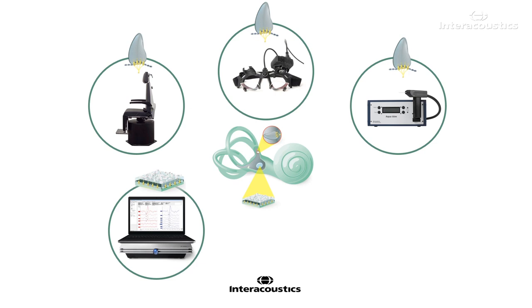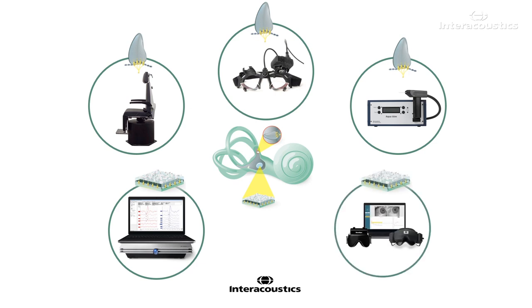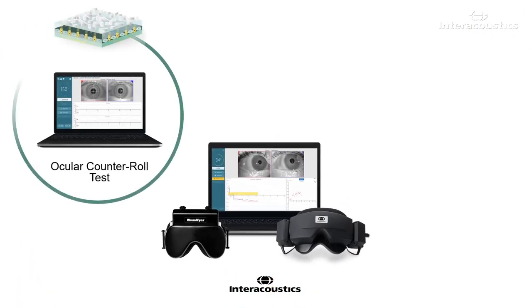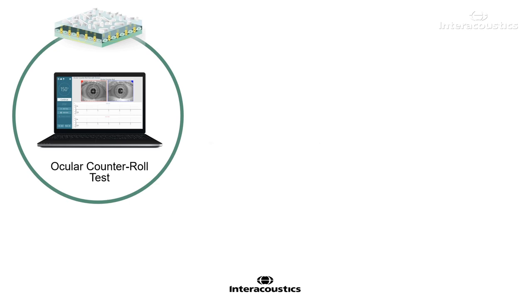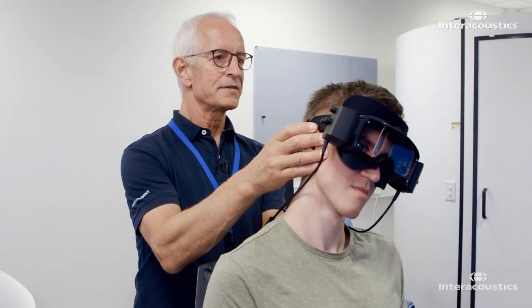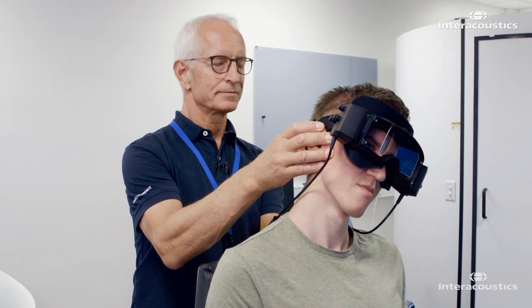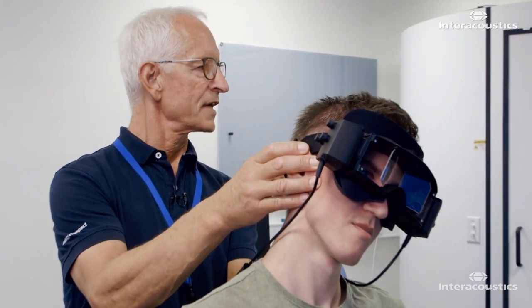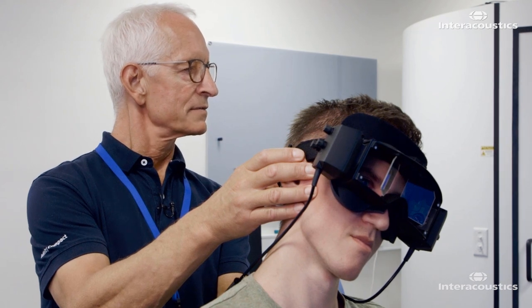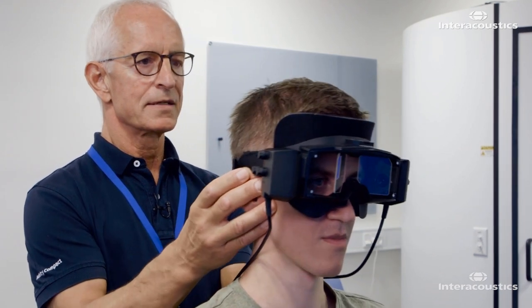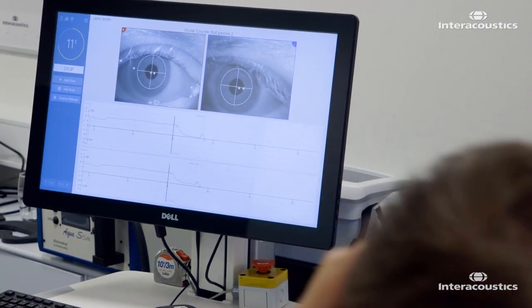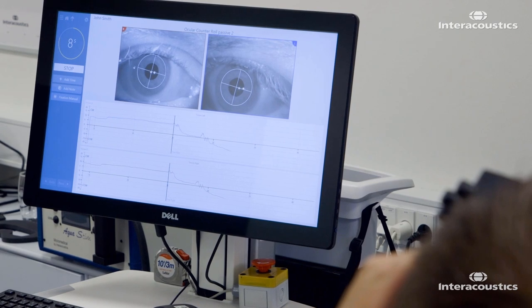The third generation of VisualEyes software offers two options for this purpose. The first one is the ocular counter roll test. It consists of tilting the head toward either the right or left shoulder in the roll plane. As you can see in this video, the head starts upright and then tilted left and held there for several seconds. Then the head is returned to the upright position and then tilted to the right.